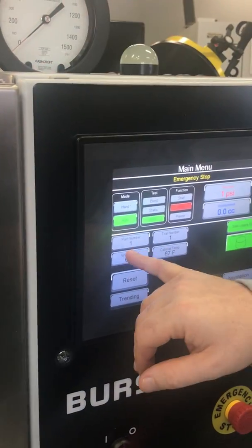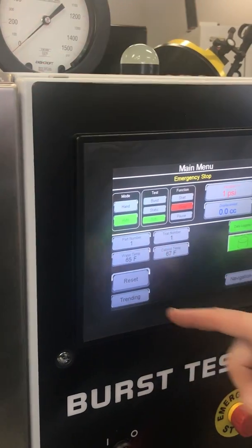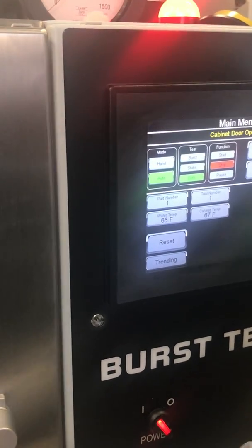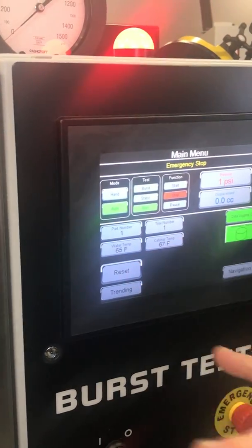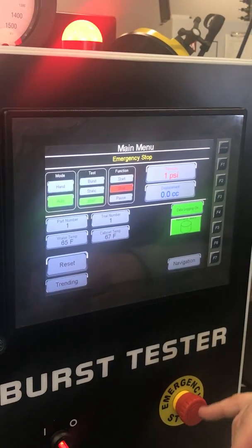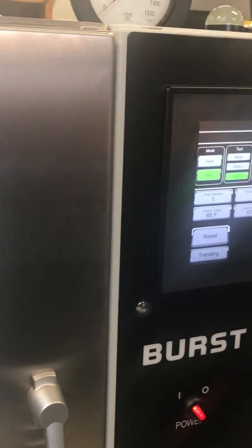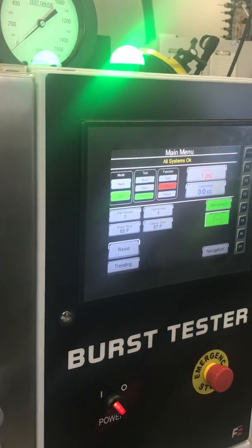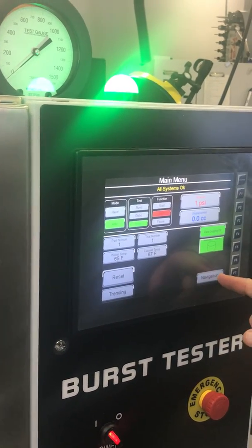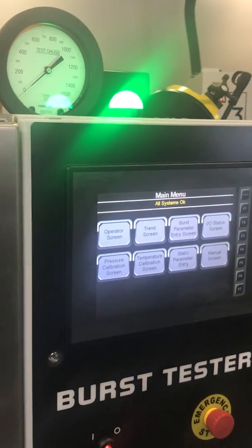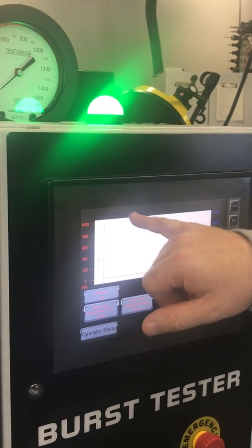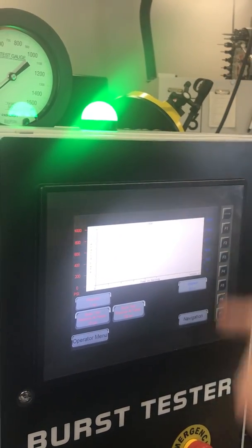Water temp, it's showing the actual water temperature and the cabinet temperature. Reset will reset major alarms. If we open that, it's going to say cabinet door open, but this is part of the safety relay. So it's reset the cabinet door, but the relay is not reset, so it says e-stop. So we hit reset. Clears the function. Navigation takes us back to the main screen again. You've got a trend screen. While we're running, you can watch the PSI and your displacement graph. That's the trend screen. Navigation again.